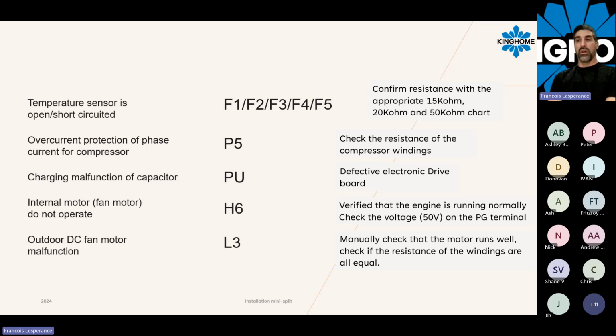P5 is also related to an overcurrent protection of the compressor. So when a P5 appears, make sure you check the resistance of your compressor windings and make sure they are not grounded. Basically, what we want to do at that point is make sure we order the right part, by checking the compressor, for example, checking the resistance directly on the windings of the compressor. That will tell you if your compressor is good or not. The resistance must be equal on each winding, and also open to ground, so there should not be any resistance to the ground.